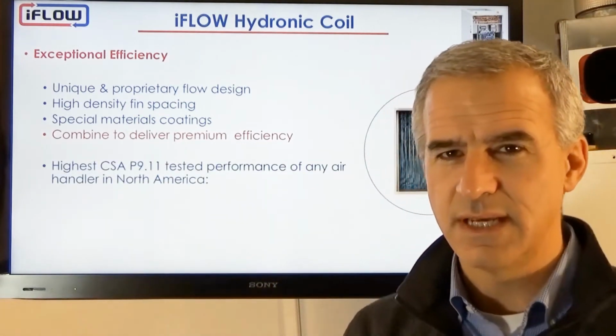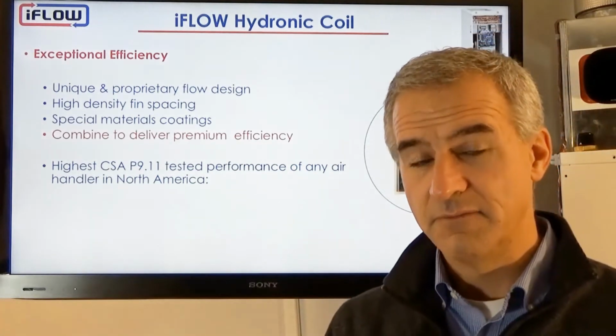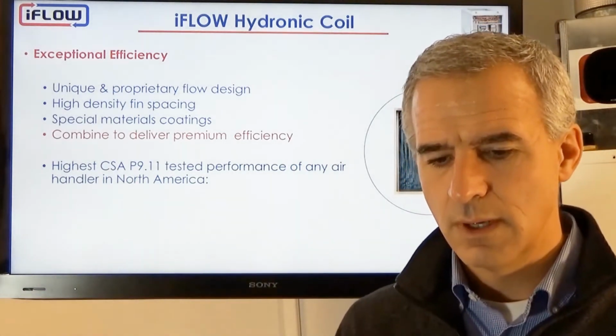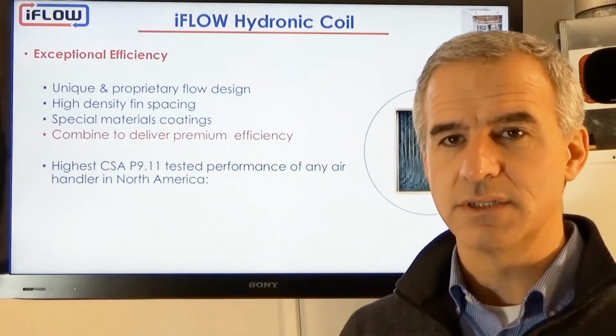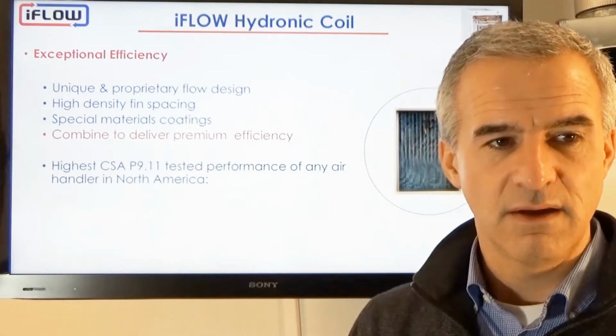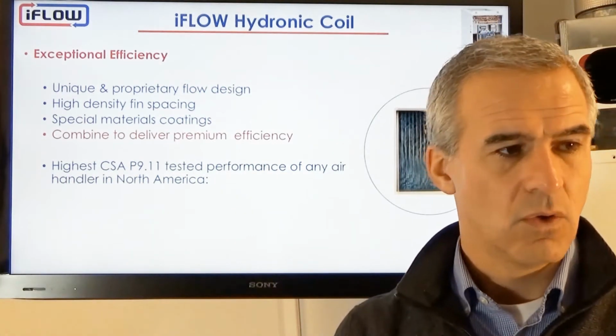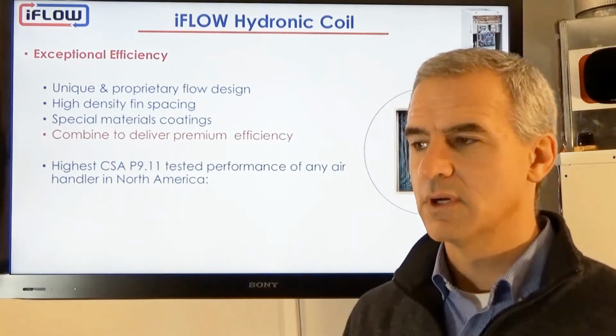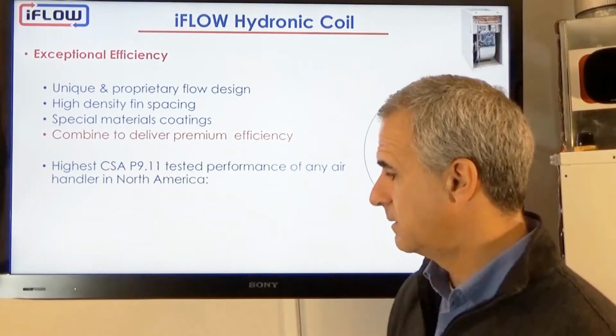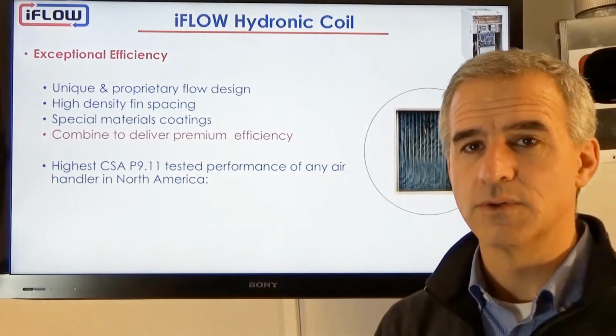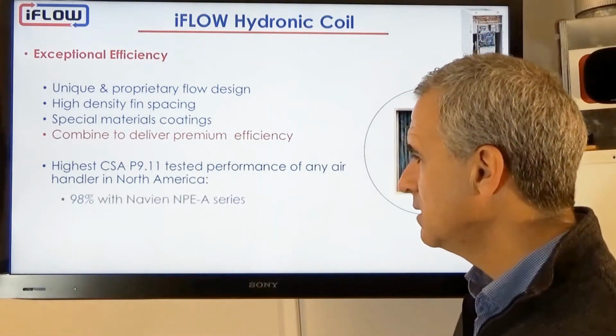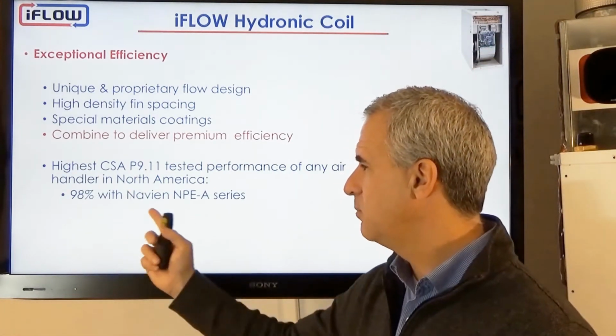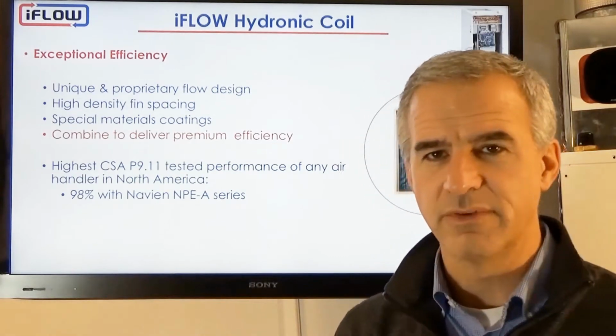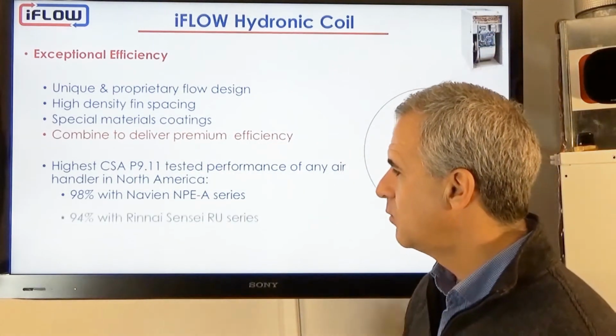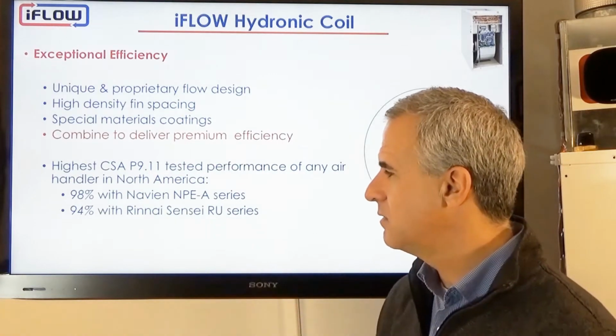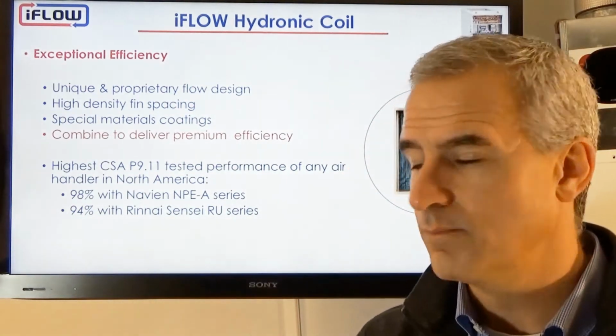When we tested to the CSA P9 standard, which is an efficiency standard that is designed to measure the efficiency of combination systems. So when we combine the iFLOW air handler with a tankless water heater or a heat pump water heater or a boiler, for example, this is the test that we would use to rate those solutions. So luckily, when we combined with the Navien NP condensing tankless series, we scored a TPF of 0.98 or 98%. And when we tested with the Rinnai Sensei RU series, we scored a rating of 94.